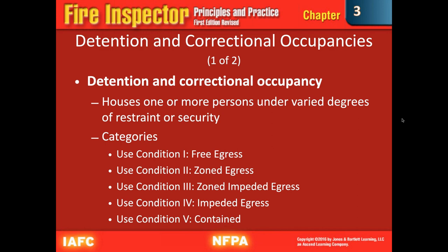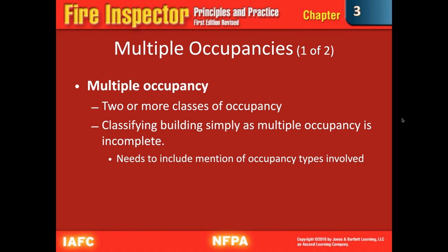Inspection focuses on the construction type, capacity, means of egress, horizontal exits, sliding doors, remote controlled release mechanisms, make sure they work, and then exit discharge. Interior finish, because that is going to change how fast the fire spreads. Protection of openings, contents, hazardous areas, your sprinkler and standpipe systems, building subdivision, how is it laid out, building services, and emergency plans.